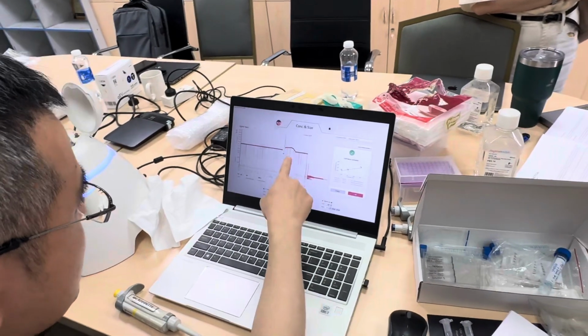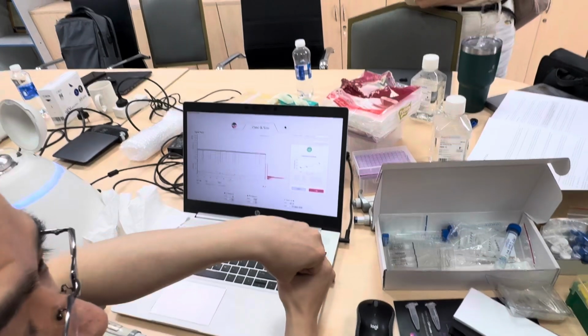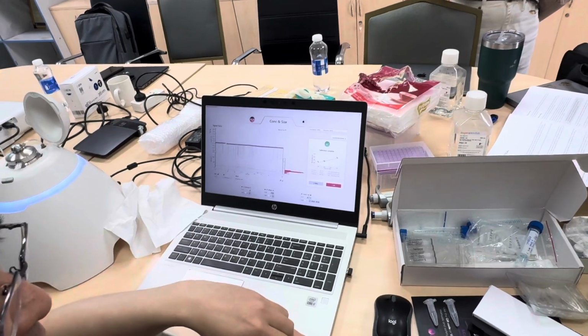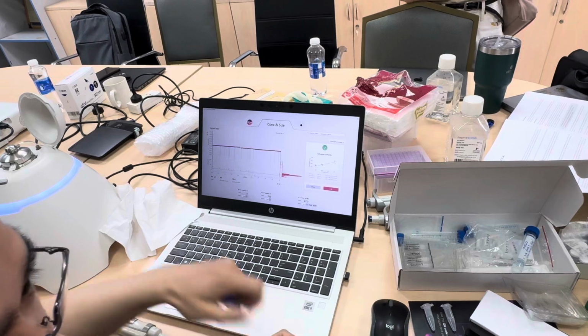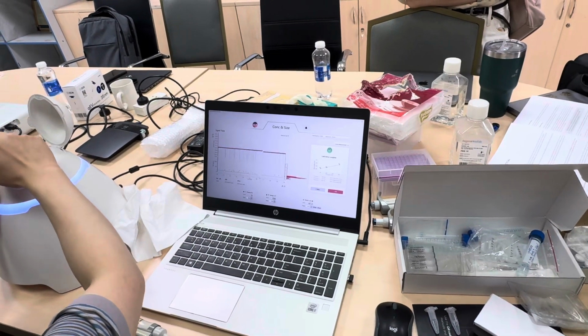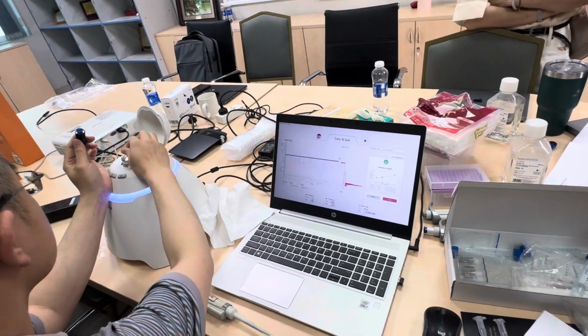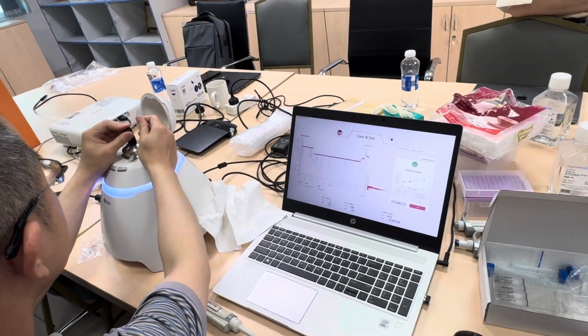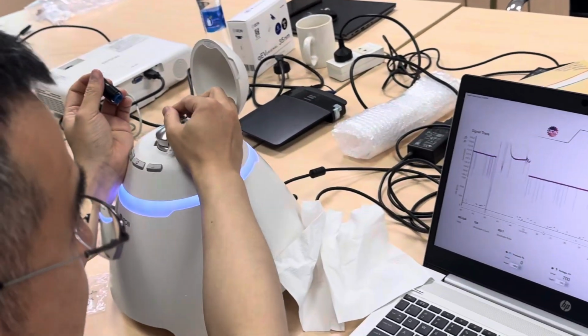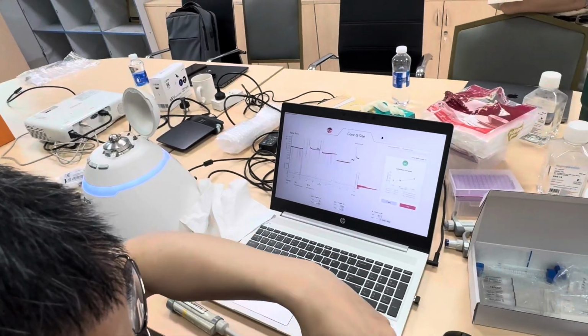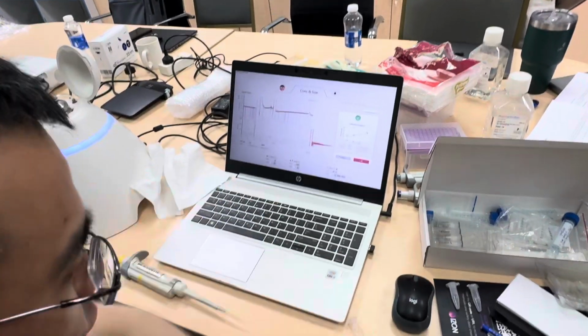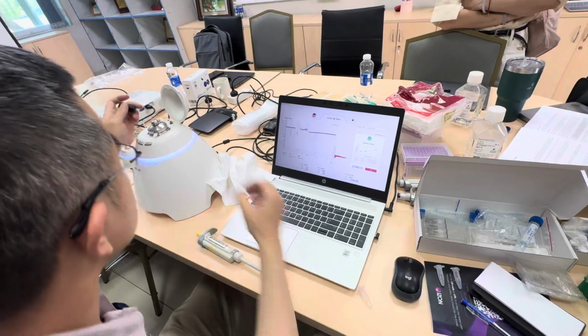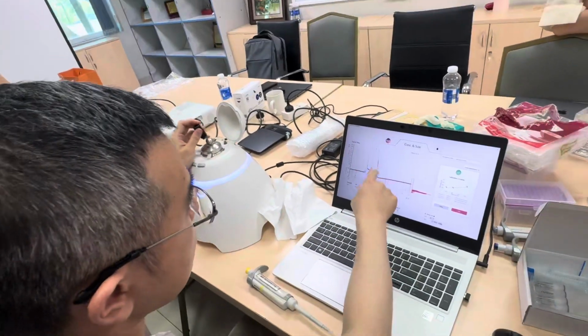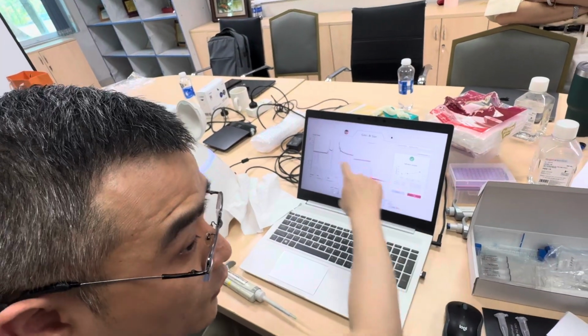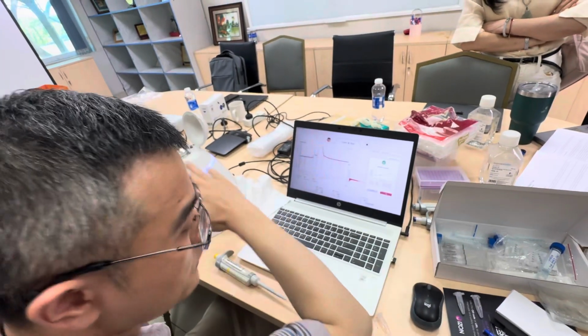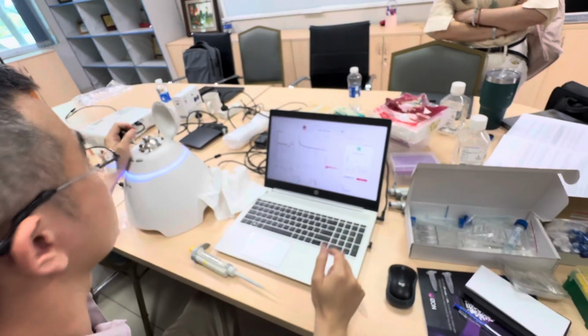And also there's a chance for the large particles to totally block the nanopore, so the current will drop a lot, maybe drop to 0. In that case, you see these 2 sides of this pressure application device. We use the plunger side to give instant pressure. It's also to encourage the blocking particles to force them through the nanopore. And then what's your intervention? You see it is different from the normal running particles. So the system will remove that data, and it won't affect your readings.